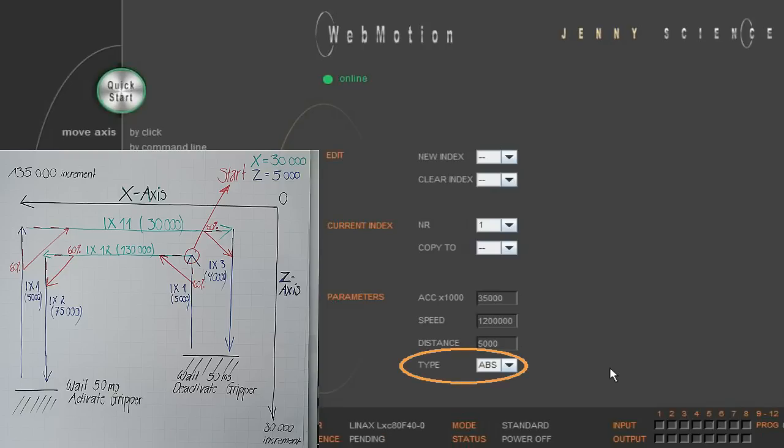Under type, you can choose to enter relative or absolute distances. However, we strongly recommend to use absolute positioning as used in this example. Because the measuring scale is precisely adjusted to the mechanical moving range, the advantage is that you don't need to calculate relative distances and moving directions.